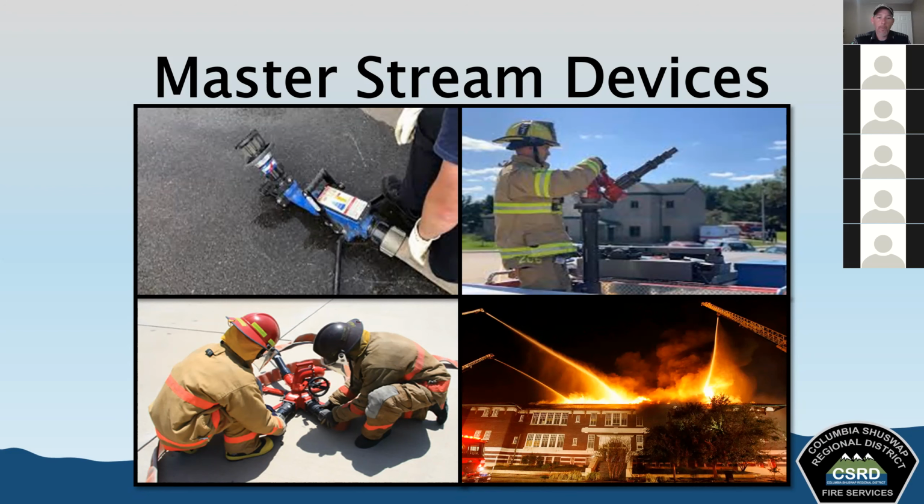Yes, I just wanted to mention, make sure that the operator communicates with the engine operator that he will be shutting down the line. It's probably better for the engine operator to reduce the pressure to stop any kind of water hammer, especially if he's elevated. Absolutely. Good communication is an important part of our water supply.